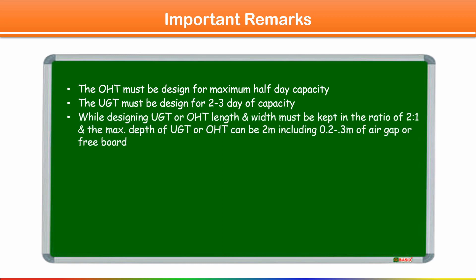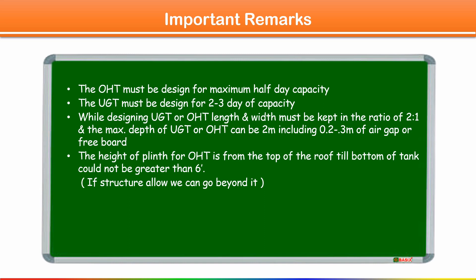While designing underground tank or overhead tank, length and width must be kept in the ratio of 2:1. The maximum depth of underground tank or OHT can be 2 meters, including 0.2 to 0.3 meter of air gap or freeboard. These points are as per the NBC and BIS standards.